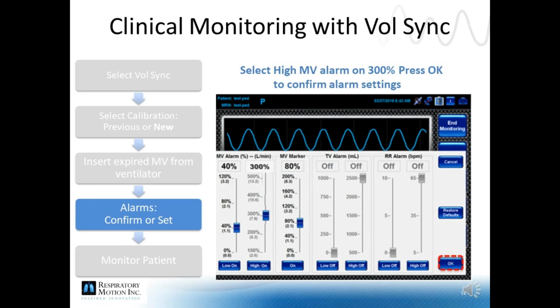This default alarm screen will be displayed while the ExSpiron is calculating patient metrics in the background. Alarm settings can be customized as needed, but most likely you will accept the current alarm settings by pressing OK. If you are concerned about alarming for high minute ventilation, as for patients with viral pneumonia, COVID-19, or congestive heart failure, you may choose to set the high minute ventilation alarm at 200 or 300%, or another designated level.